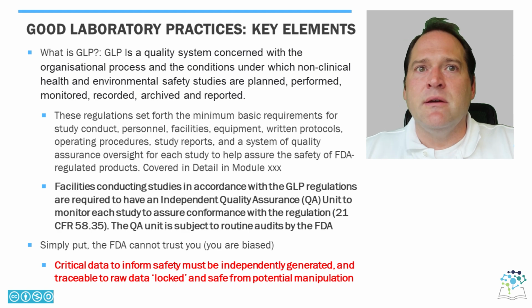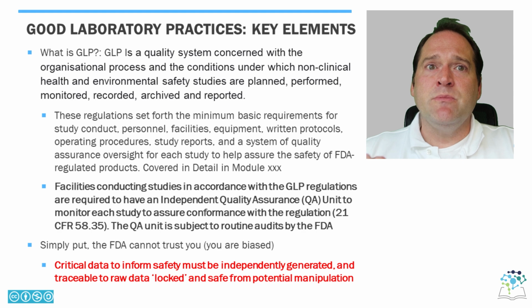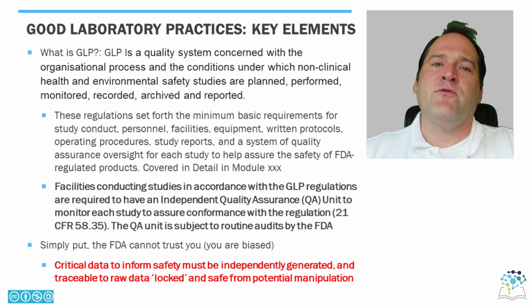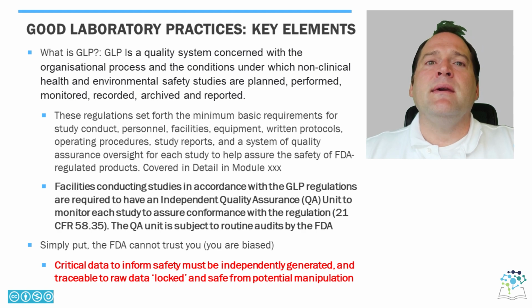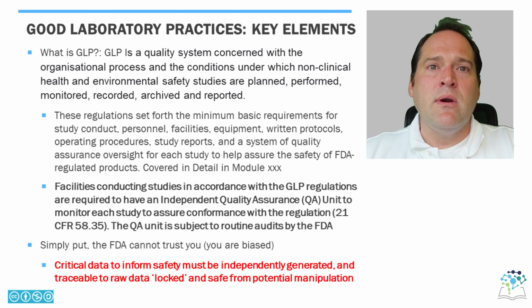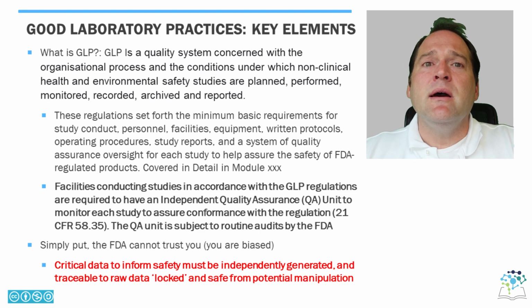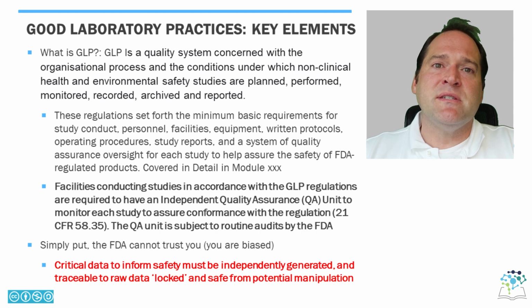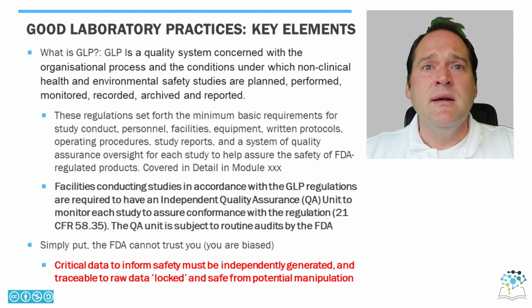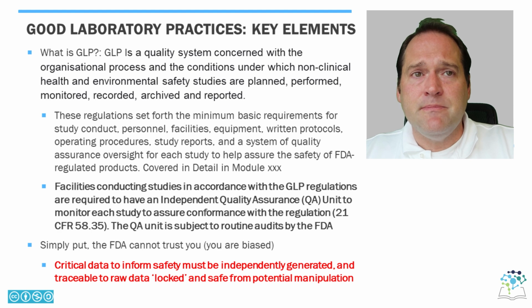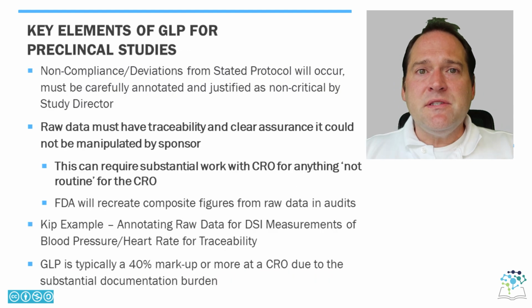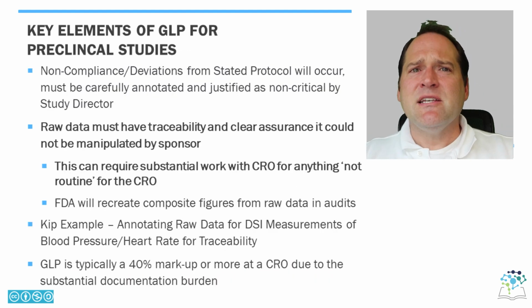So critical data to inform safety must be independently generated and traceable to raw data, locked and safe from potential manipulation. And the FDA will come in when you have an IDE submission or when you have a PMA or 510(k) submission and sometimes ask to recreate, from this independently locked raw data, key analysis that you used. So what does this mean, and what are key aspects of GLP?